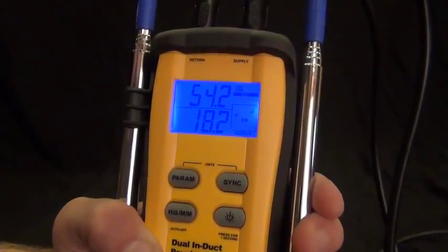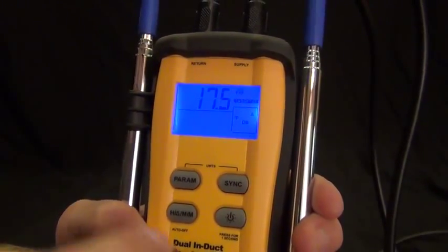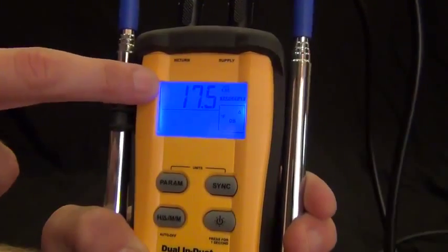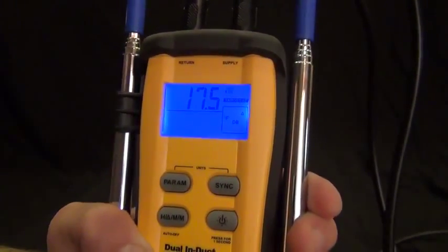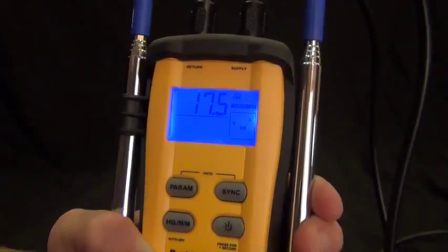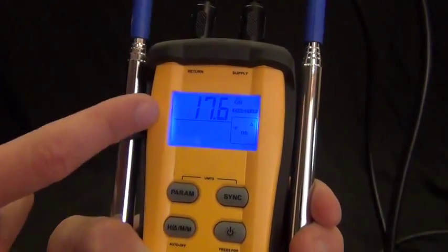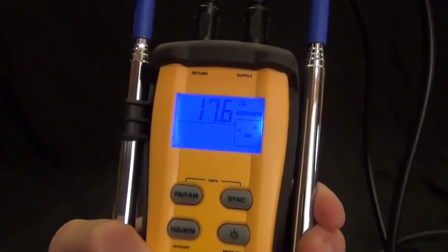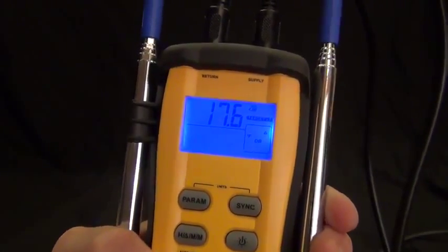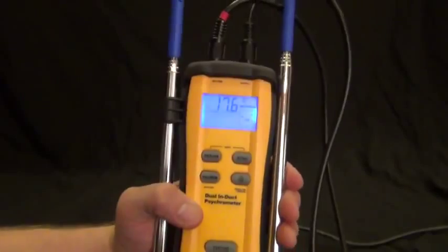Now on the target delta T, I can put it up here and this is basically saying based on the conditions I'm giving it of the return wet bulb and the return dry bulb, my temperature drop should be 17 degrees. So those two tests are roughly, they're basically the same test, just formatted differently.